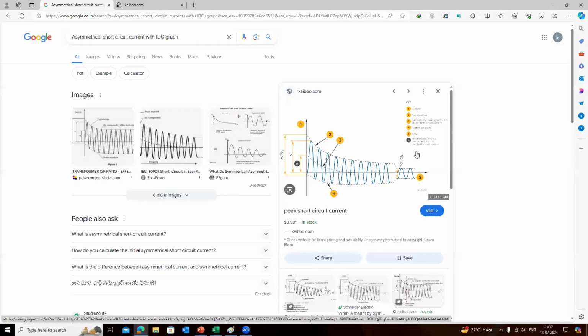If you see this image here, at the first instant, 1 or 2 cycles, the fault current is different. And here the fault current is different. Here the fault current is different. And once it gets settled down, this is the steady state current. So the steady state current will remain the same irrespective of the instant at which the fault is happening. Whereas the other components like IK double dash, IDC, IK dash are varying with respect to time, and with respect to the instant at which the fault happens.